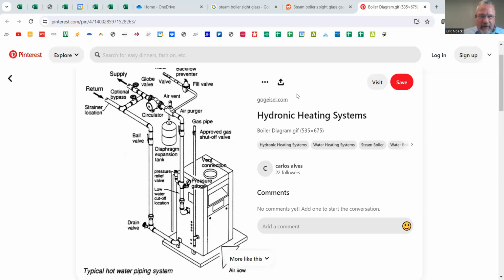But one of the keys here is if you follow that water line, the water line is going to come off near the water heater sometimes, or you're going to be able to see that it's an actual water supply line and not a boiler pipeline. So it's going to come in, and when it's done properly, what we see here is a proper setup. Now, what's important to remember is all this stuff around here is called trim. All the extra parts that are connected to a boiler are referred to as trim. There's the exact textbook way it should be done, and then there are some variations to that, and then there's some stuff that looks really messed up that does still work sometimes that people have done over the years. That's where it can get a little tough to understand what's going on, because these things can be done in a lot of different ways. But this is really the right way here.